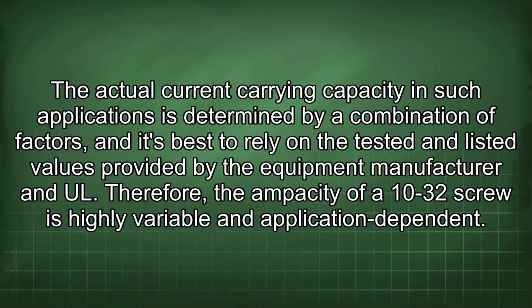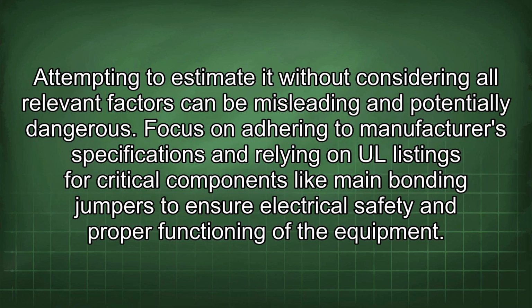Therefore, the ampacity of a 10-32 screw is highly variable and application dependent. Attempting to estimate it without considering all relevant factors can be misleading and potentially dangerous. Focus on adhering to manufacturer's specifications and relying on UL listings for critical components like main bonding jumpers to ensure electrical safety and proper functioning of the equipment.